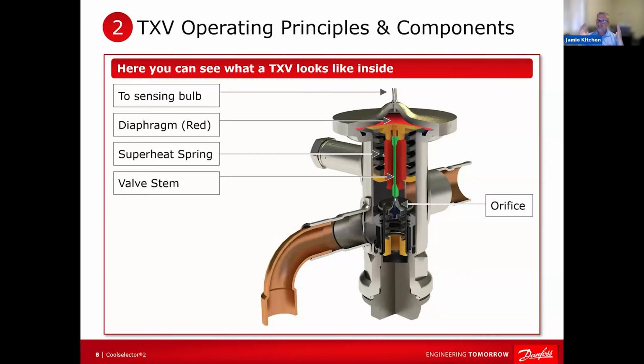Now, brazing in an expansion valve is not something you can just do like this, right? It takes practice. It takes a talented torch a lot of times, because they can be a miserable thing to braze in, these big brass body valves. If you've got the extended ends, fantastic. Otherwise, you're wrapping this thing with wet wrap, with paste, and it's a fight against time to get it in, because it's trying to evaporate the heat you're applying, and you're trying to heat it up before it overheats, right? Not fun. You've got to practice this stuff.